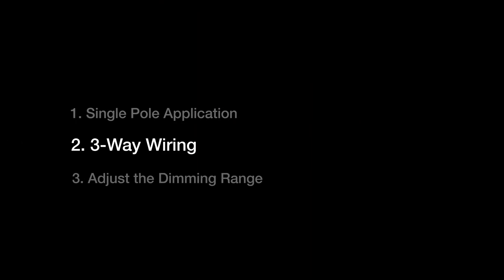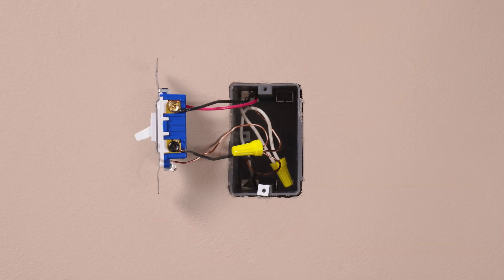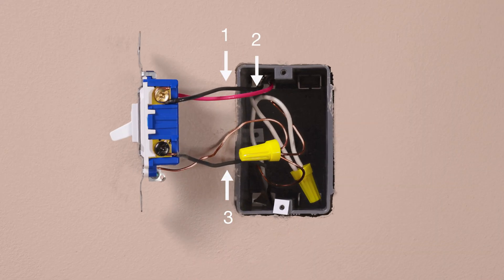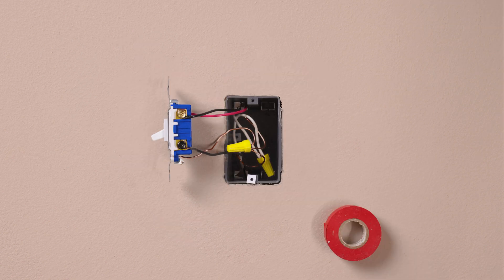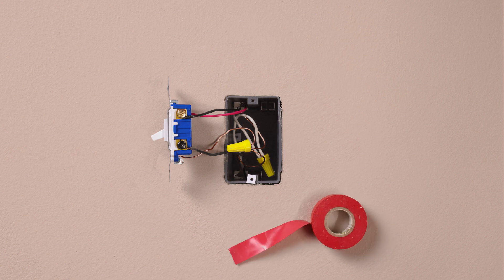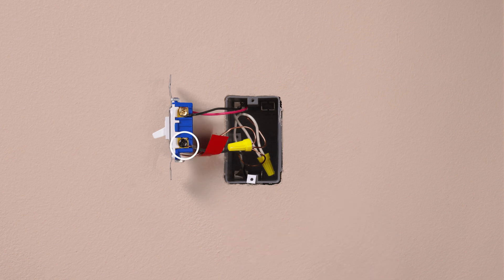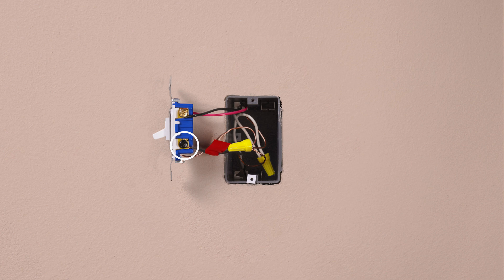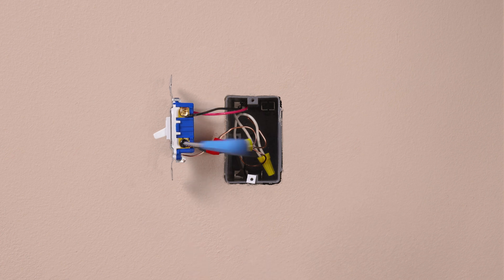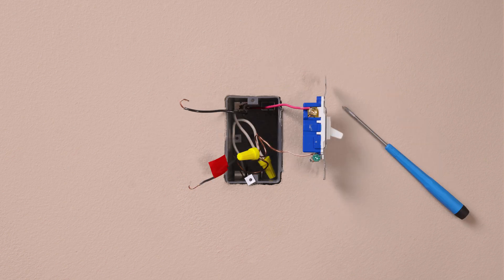If you have two switches that control this light, you should have three wires plus a ground connected to your old switch. Take a piece of electrical tape and tag the wire connected to the different colored screw of the existing switch. This is typically a black wire. Then disconnect and remove your existing switch.